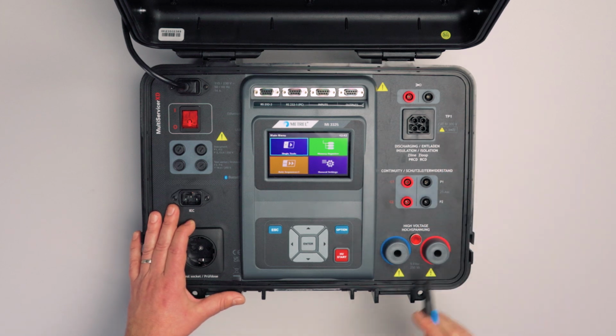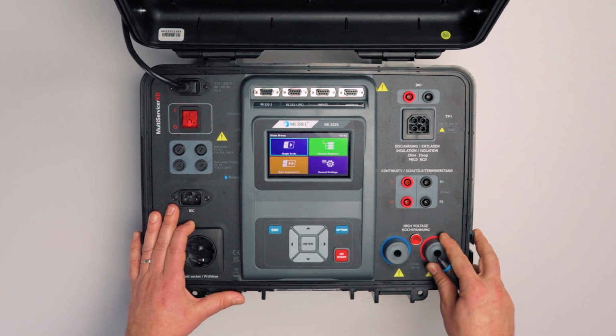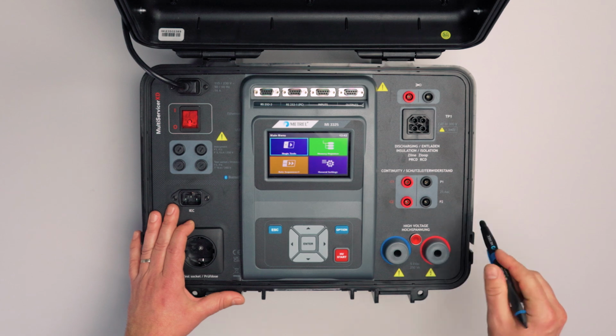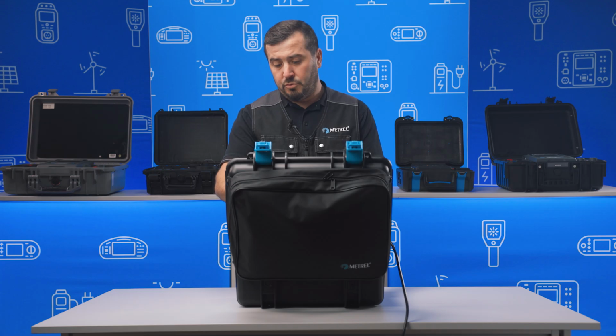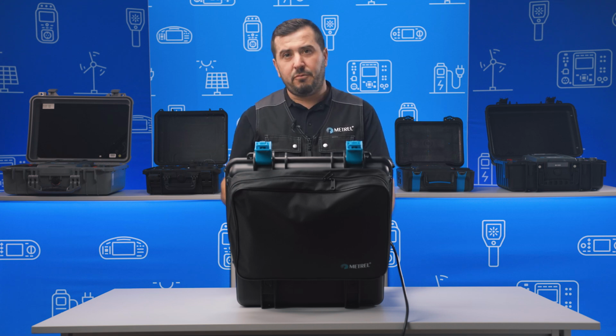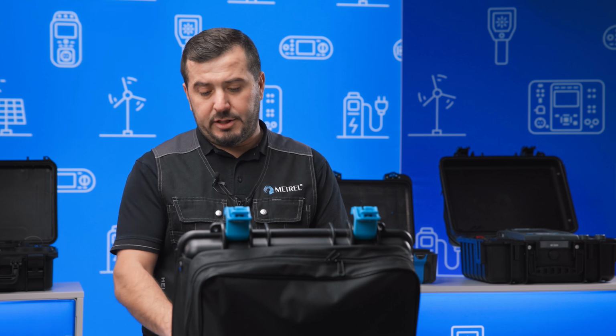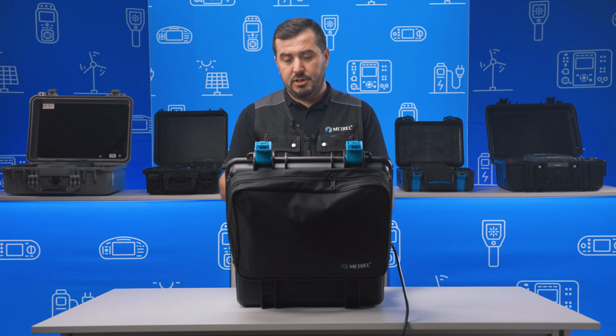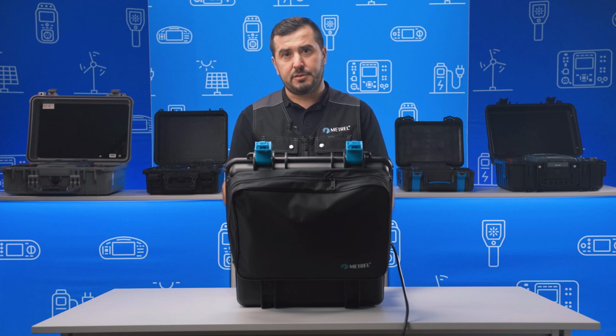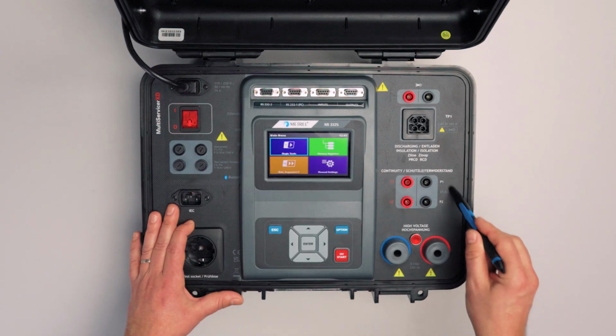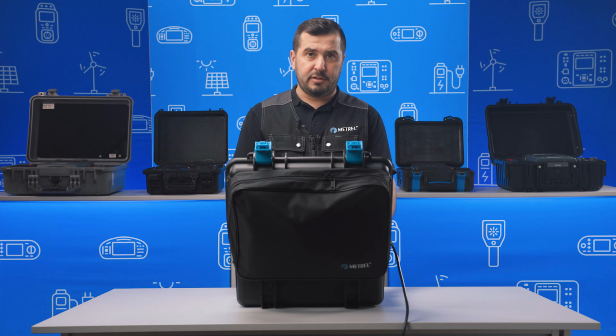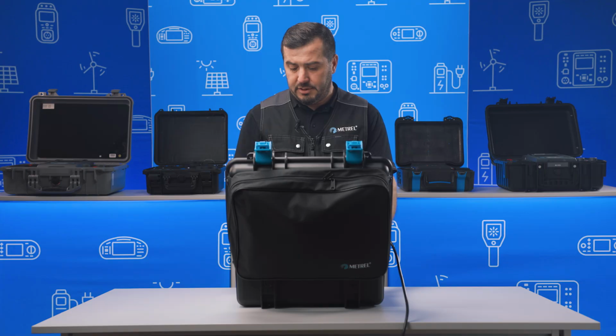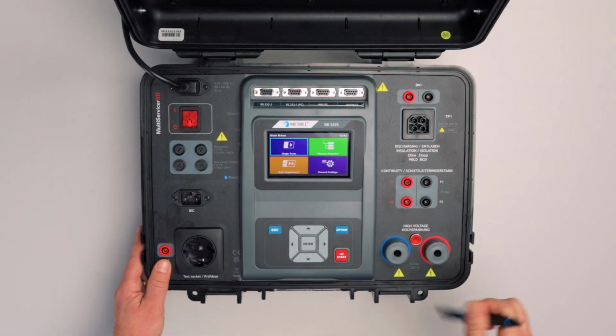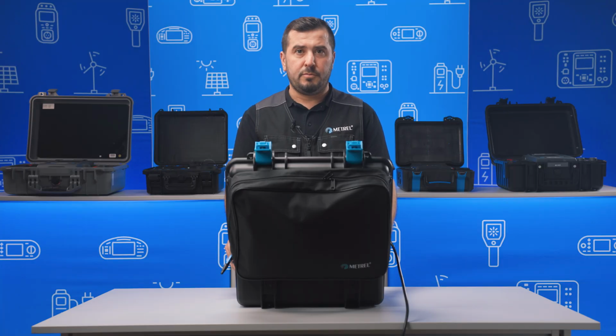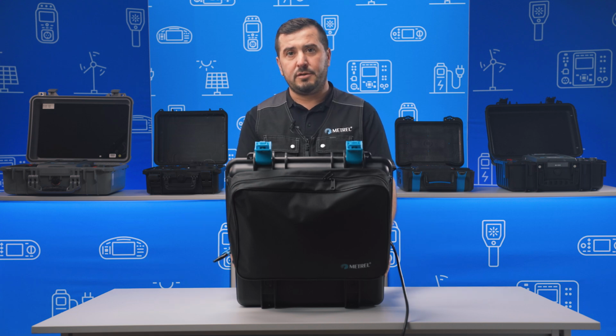If we focus on the right side of the instrument, at the top there is a special port dedicated for connecting optional current clamps and a multi-purpose TP1 connector to which we can connect the test cable for measuring residual voltage or the universal 3-wire and Schuko cables for testing either discharging time, so the residual voltage, insulation resistance, or line loop impedances plus the RCD testing. The next one is the continuity test terminal, where we connect the 4-wire testing leads for testing, of course, 4-wire continuity. And the last one is the high voltage test terminal, from where we can perform the high voltage test with up to 5.1 kilovolts AC.